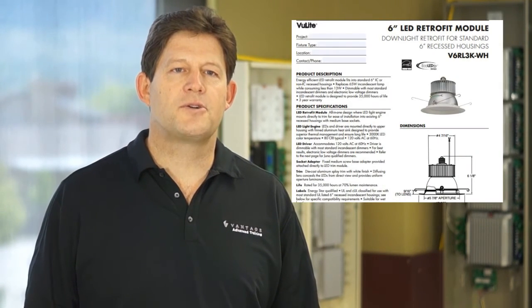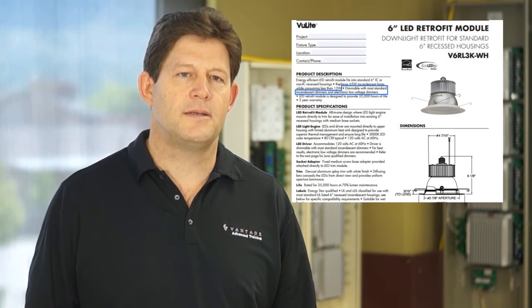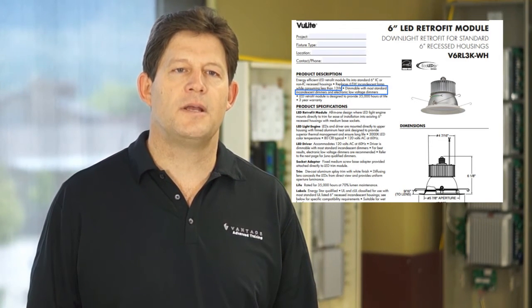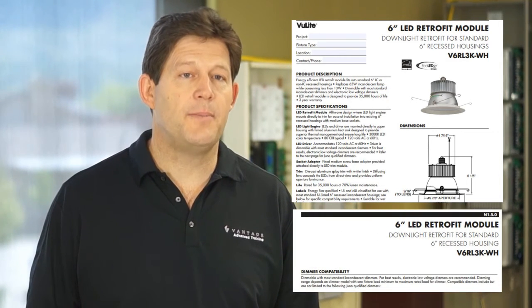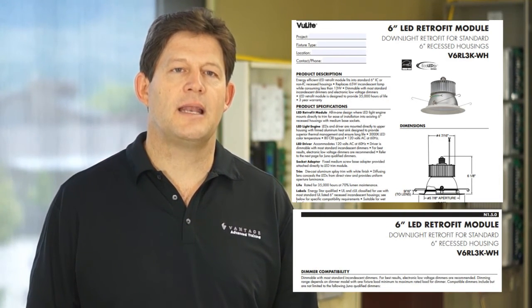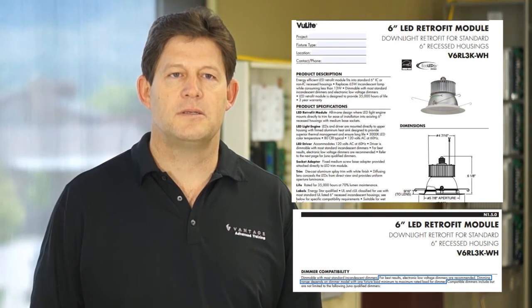In this example, the product description states that the product is dimmable with most standard incandescent dimmers and electronic low-voltage dimmers. Further along, there is a dimmer compatibility statement that clarifies that electronic low-voltage dimmers are recommended for best results. Without reviewing the entire document, I might have been inclined to assign loads to the standard dimming module. But with this additional information, I would definitely assign to an electronic dimming module.